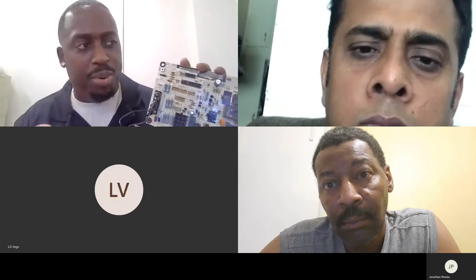Let's say it's a heat pump. A heat pump has what's called a reversing valve. And now that I see everything's working, I want to energize the reversing valve and make sure that's working. Boom, I got a whole extra alligator clip. This board does not have an O terminal for a heat pump because it's not for a heat pump system. So we're just gonna pretend this is O. I can connect there, and then you'll hear the reversing valve. It's a real distinctive sound. You'll know when we get to that point. But now I can connect that. I can see if I can hear my reversing valve engage, and now I've just tested different circuits with my jumpers. So that's the point of having jumpers.